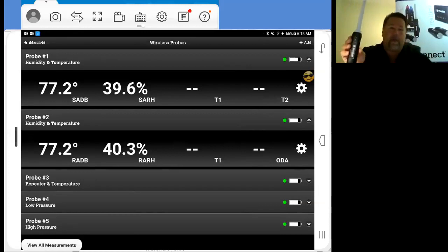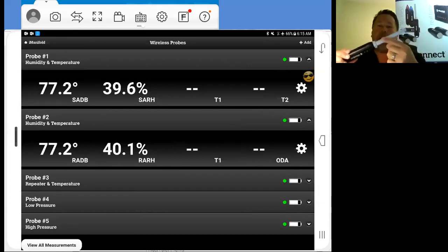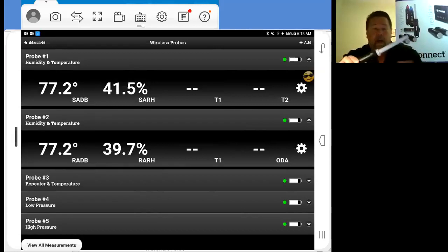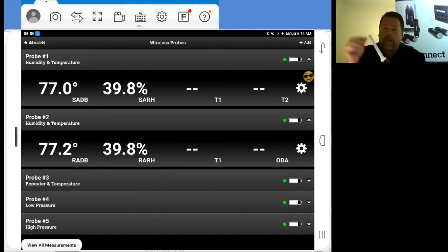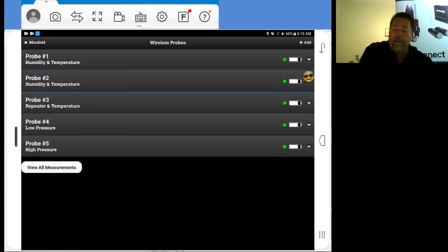That's what it's winking. So this one being the supply, what you may want to do to identify and keep it identified is just put a piece of tape around the probe itself. You can put a little blue piece of tape or whatever piece of tape that would obviously tell you if it's supply or return, or you can just simply put a mark on here and use an S on here, write supply on there, however you want. So identifying the probe is very easy. If you need to switch them around, very easy to do as well.